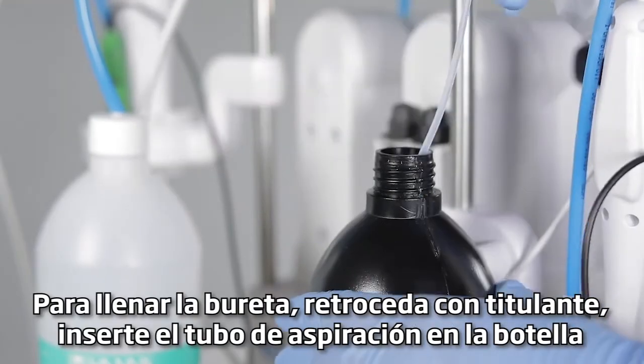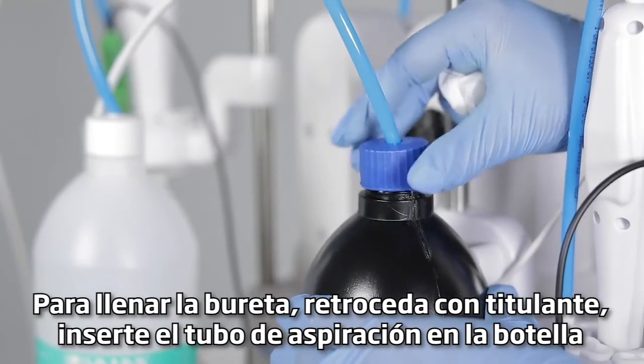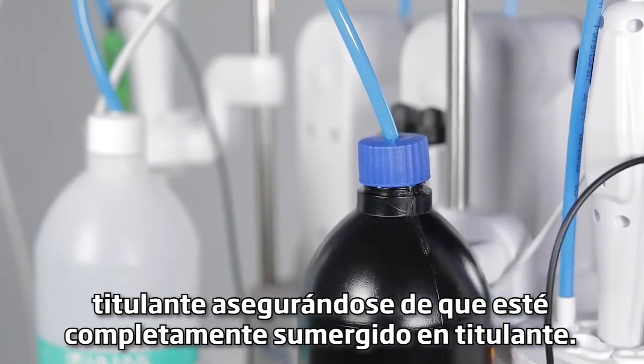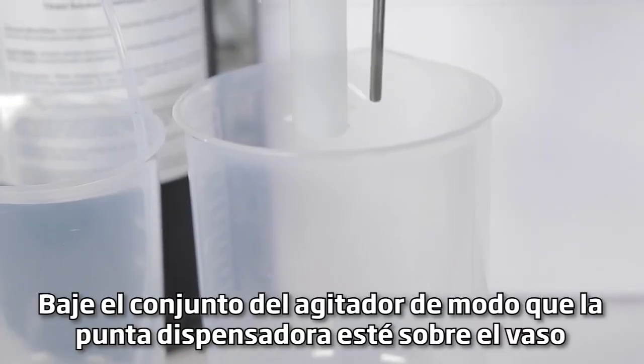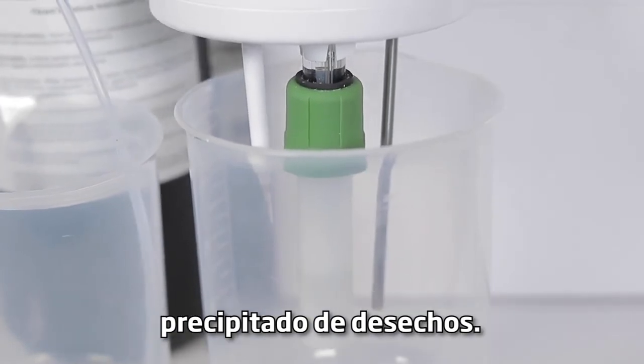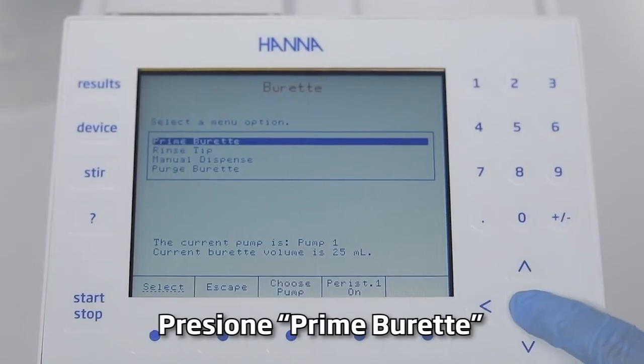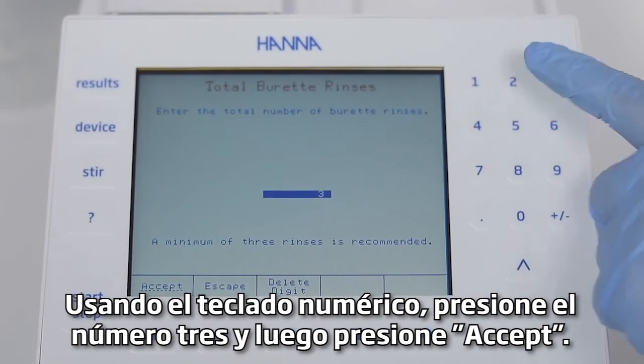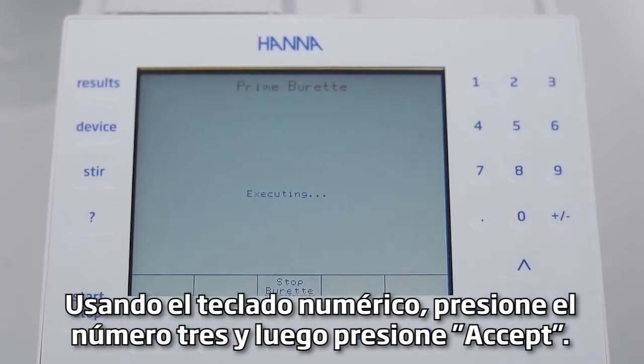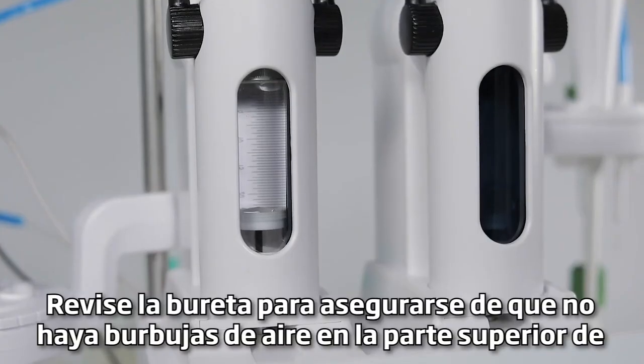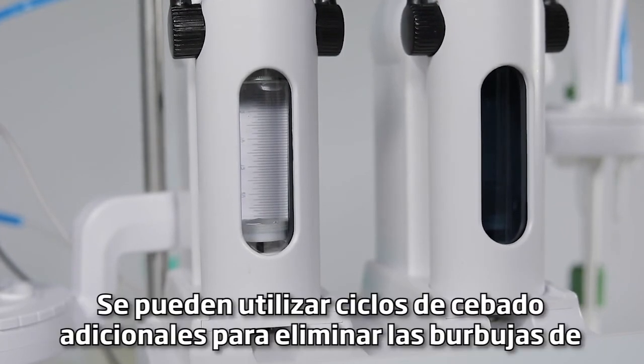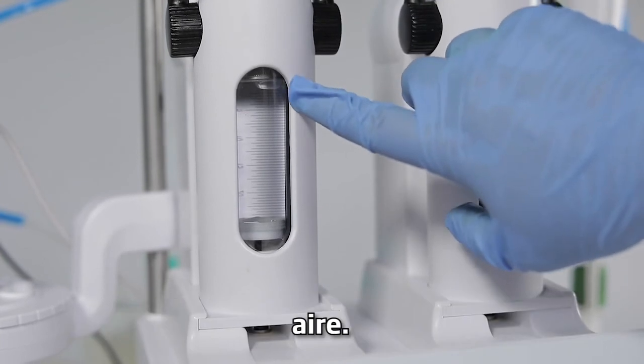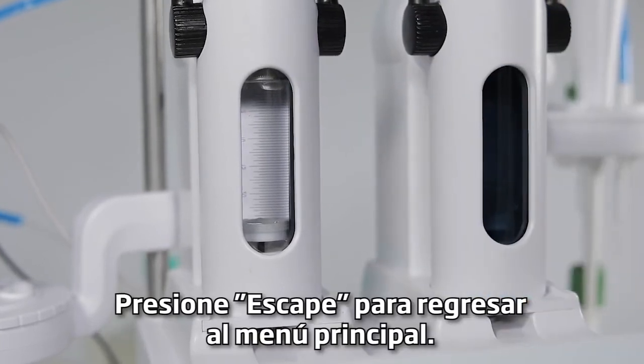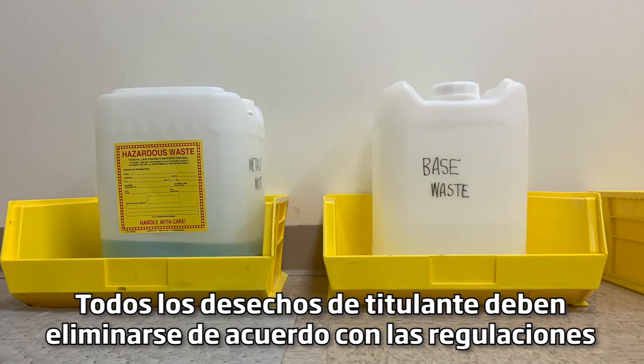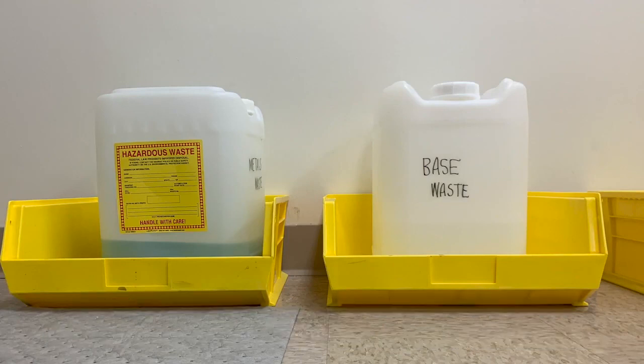To fill the buret back up with titrant, insert the aspiration tube into the titrant bottle, ensuring that it is fully submerged in titrant. Lower the stirrer assembly so that the dispensing tip is over the waste beaker. Press Prime Buret. Using the number pad, press the number 3, then press Accept. Check the buret to ensure that there are no air bubbles at the top of the syringe. Additional prime cycles can be used to remove the air bubbles. Press Escape to return to the main menu. All titrant waste should be disposed in accordance with your local regulations.